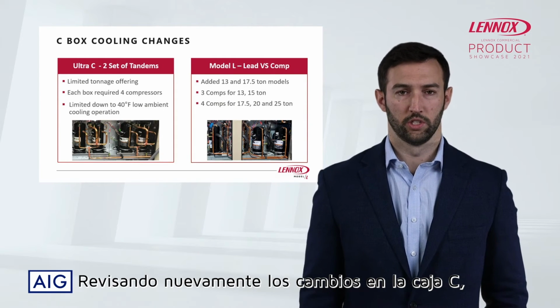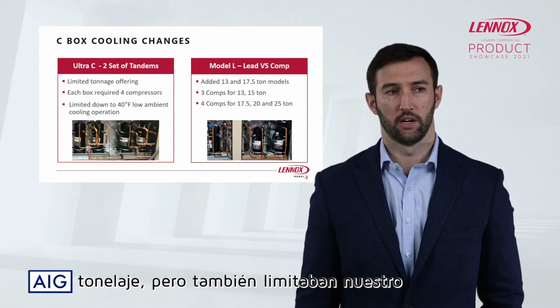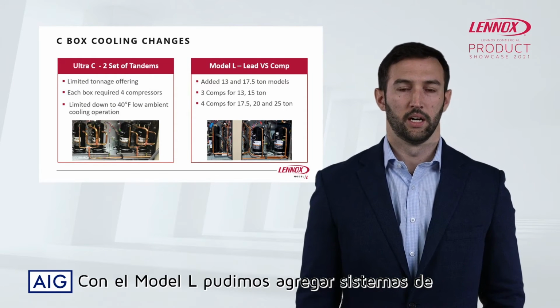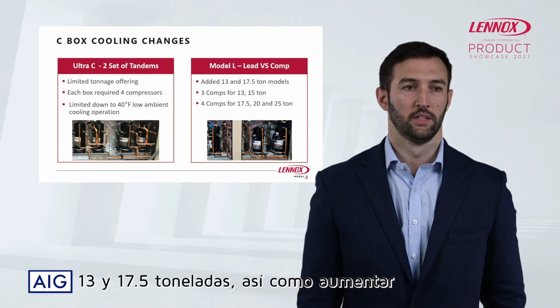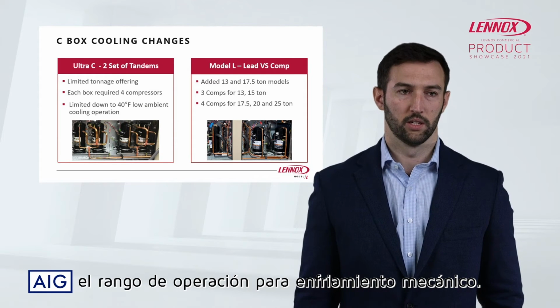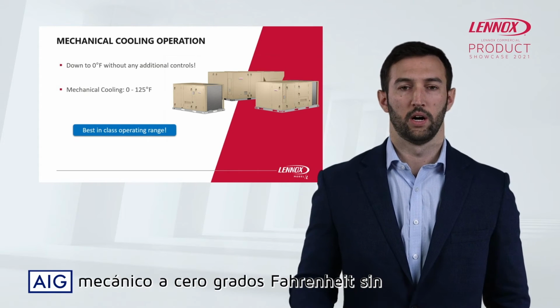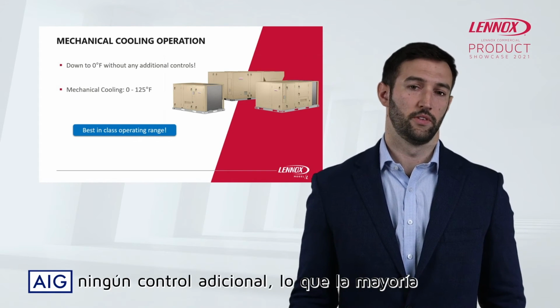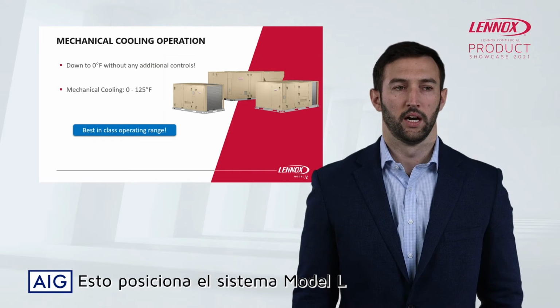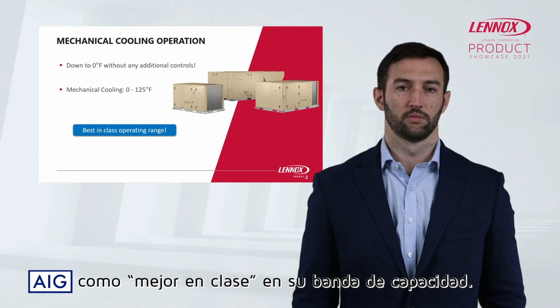Looking again at the C-box cooling changes, we used to have two sets of tandem compressors that again limited our tonnage offering, but also limited our low ambient cooling range. And so with the introduction of Model L, we were able to add 13 and 17.5 ton models, as well as increase that operating range for mechanical cooling. And so, like I said, we were able to operate mechanical cooling down to 0 degrees Fahrenheit without any additional controls, which most competitors are not able to match. And this gives us a best-in-class operating range for cooling with the Model L units.